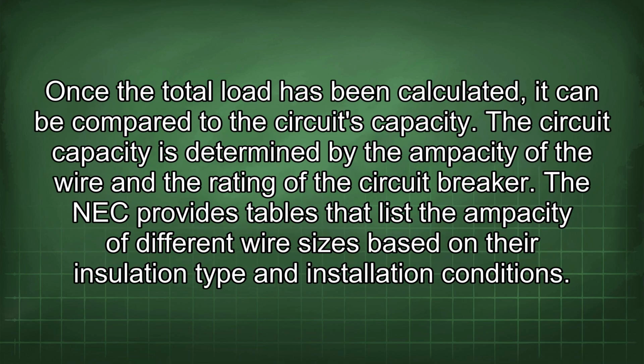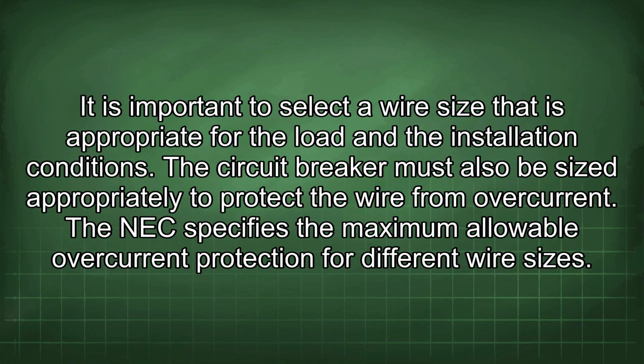Once the total load has been calculated, it can be compared to the circuit's capacity. The circuit capacity is determined by the ampacity of the wire and the rating of the circuit breaker. The NEC provides tables that list the ampacity of different wire sizes based on their insulation type and installation conditions. It is important to select a wire size that is appropriate for the load and the installation conditions. The circuit breaker must also be sized appropriately to protect the wire from overcurrent. The NEC specifies the maximum allowable overcurrent protection for different wire sizes.